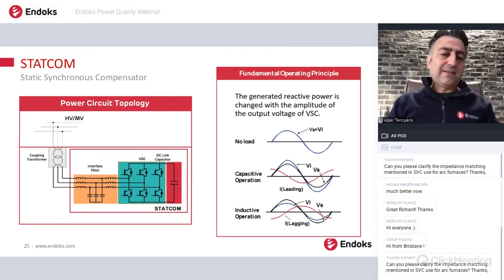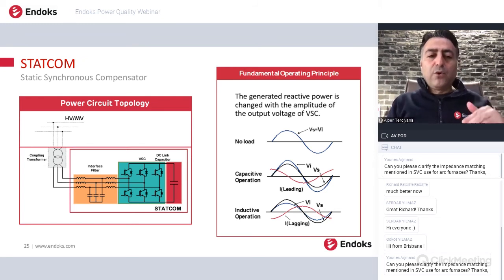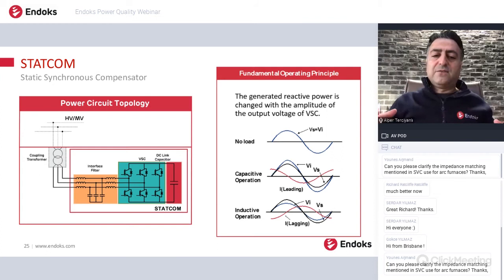You see on the STATCOM on the left-hand side, we have a capacitor on the DC link of the STATCOM, the DC link capacitor. We have a converter, we have a filter circuit, and a coupling transformer in order to connect the STATCOM to the medium voltage or the high voltage. So STATCOM is acting as a voltage source, and this voltage source is mainly in the same phase with the supply voltage, but the magnitude generated by the STATCOM can be controlled, and it can be lower or higher than the supply voltage. If it is lower, then the inductive reactive power is flowing from the grid to the STATCOM, or if the voltage is higher, then the current is injected from the STATCOM to the grid.